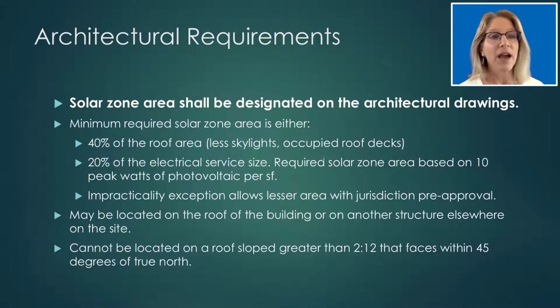So do note that. Also, the actual area that's designated for the solar array may be located on the roof of the building, or it can be on another structure elsewhere on the site. And it cannot be located on a roof sloped greater than 2 to 12 that faces within 45 degrees of true north. And that is actually a detail we'll be looking into a little bit more. If that is the case for your building, if that's the slope of your roof, and that is all you have available, then that would be something that you might be able to coordinate with your jurisdiction to find out what would be feasible for that particular site.